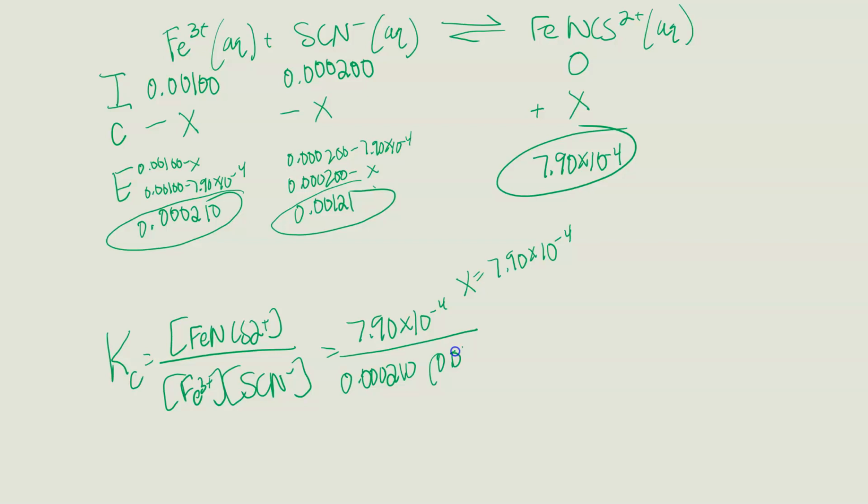And when you do this, your equilibrium constant, like for my example, it was 311. That's in the range of what it could be. Everyone's could be slightly different for your equilibrium constant, but probably in the hundreds. Probably 200 to like 800 would be my guess on what they are. It depends on what the temperature in the room was. It depends on which instrument you're using, etc., etc.